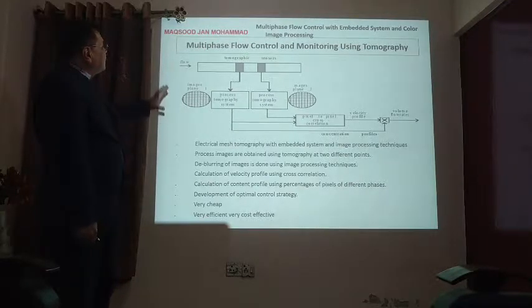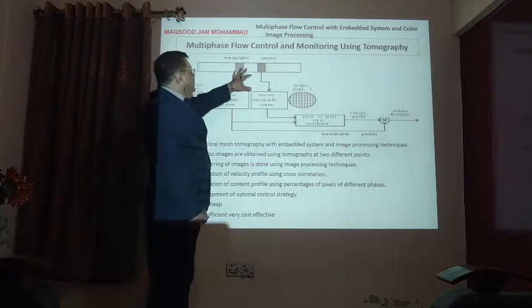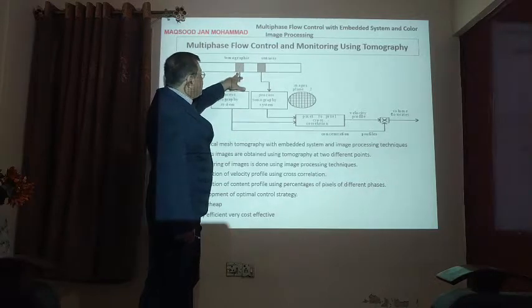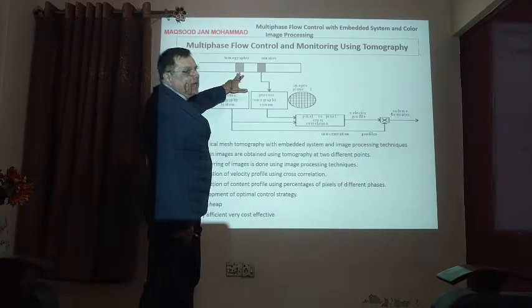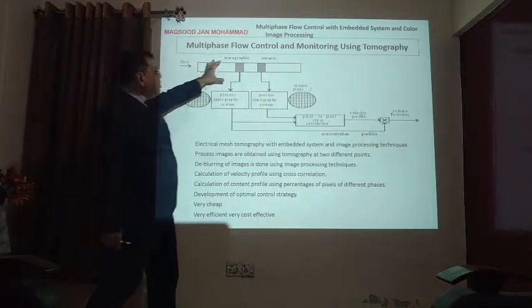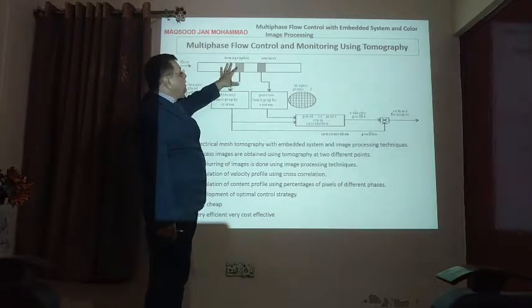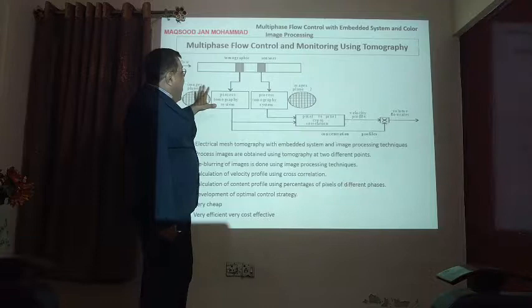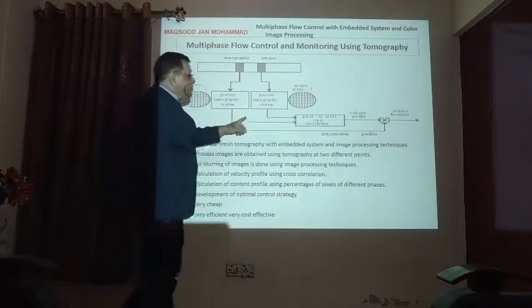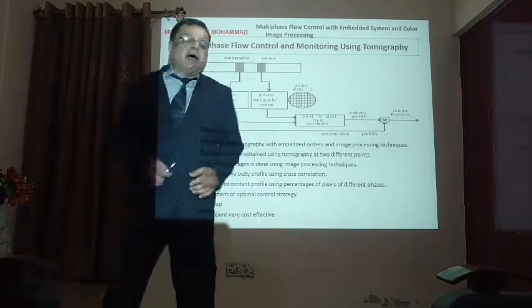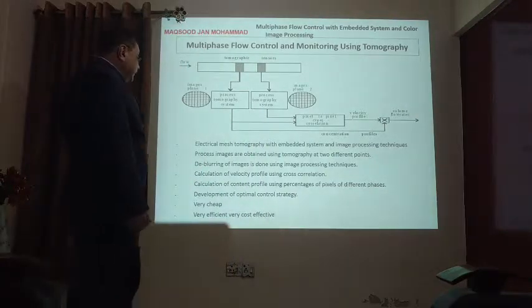The whole plant is installed on a pipe. At two places, we put sensors and capture data. This is a wireless tomographic sensor. Instead of this, we can use electrical capacitance tomographic sensors, as well as high resolution cameras of 20 megapixels or 100 megapixels. We get images through these sensors. Using pixel-to-pixel correlation, we can find out the velocity profile, content profile, and volume profile of the oil, gas, and water. We use electrical mesh tomography with an embedded system and image processing.